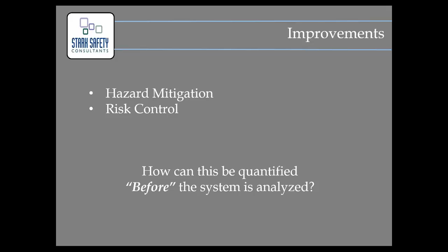Another big consideration for ongoing updating of your study is how often and what things we should be looking for. There is language in NFPA 70E regarding updating, in section 130.5.2, and there are actually 2 items. The first is that the study needs to be updated when a major modification or renovation takes place. The second is that it shall be reviewed periodically at intervals not to exceed 5 years to account for changes.